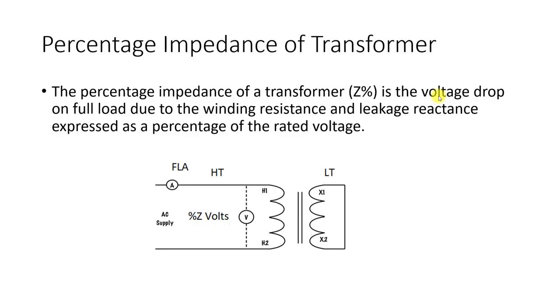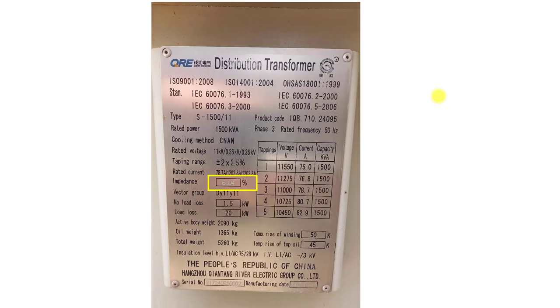Percentage impedance of a transformer is a very important parameter for power transformers and distribution transformers. It is represented by the letter Z with a percentage sign. You will be amazed that it is not measured in ohms — this percentage impedance is measured in voltages, or you can express it in per unit. The percentage impedance is the voltage drop at full load due to winding resistance and leakage reactance, expressed as a percentage of the rated voltage. Looking at a transformer nameplate, you can see the percentage impedance listed.